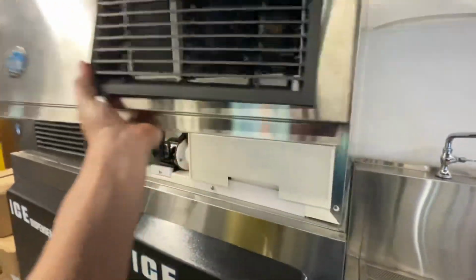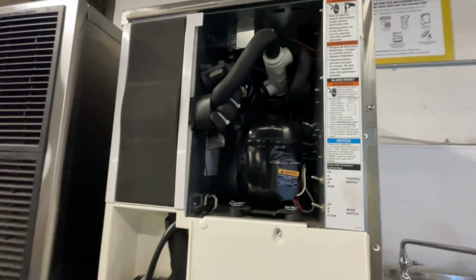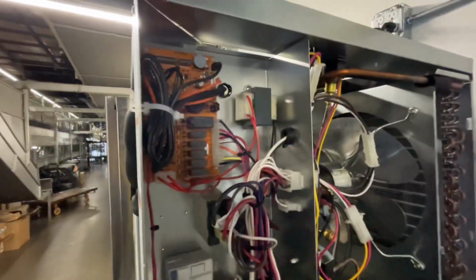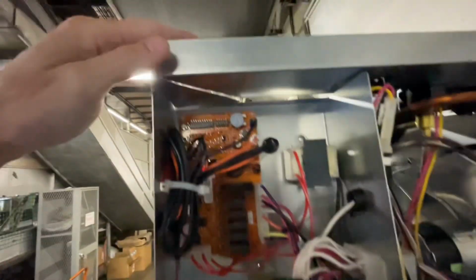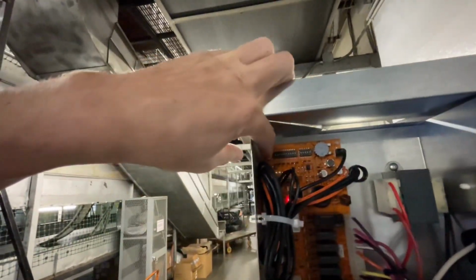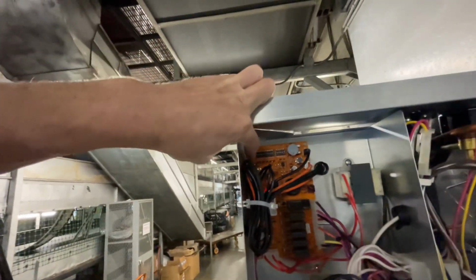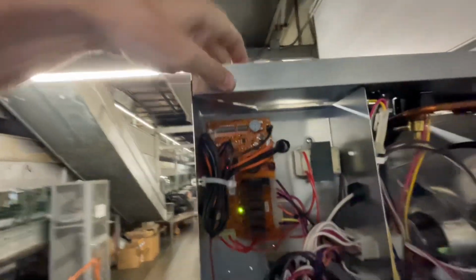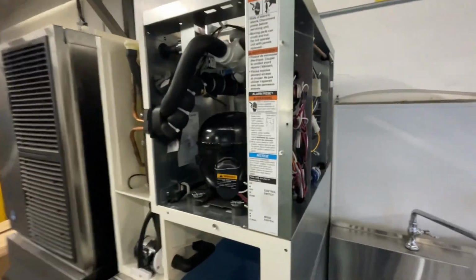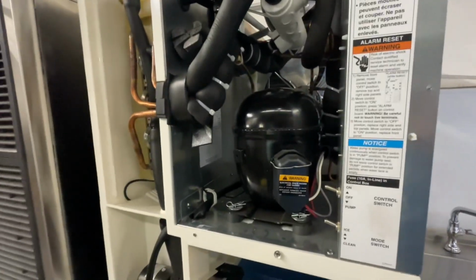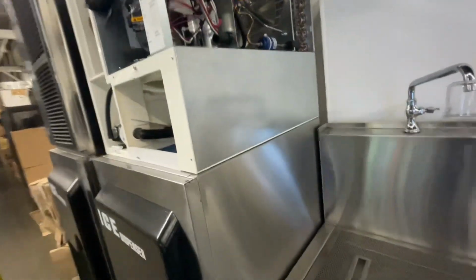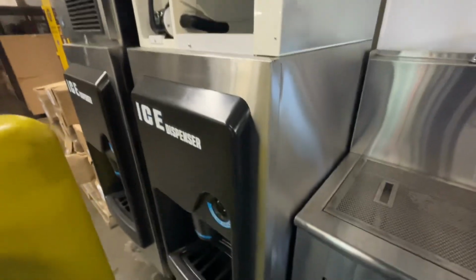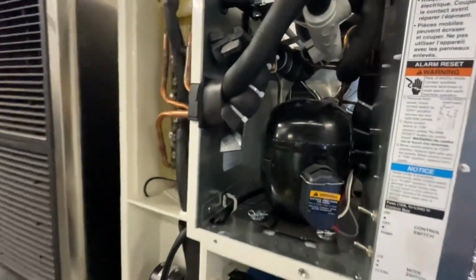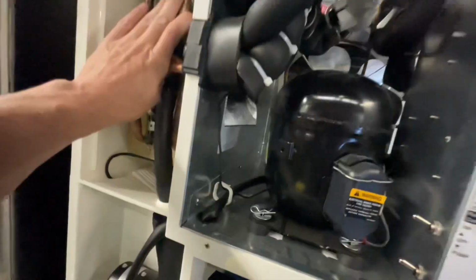Let's see why this thing is beeping 2 times. For those who don't know, this machine is off on 2 beeps, which means, if I can get this to reset, that harvest time exceeded 20 minutes for 3 cycles in a row. We gotta double check. All right, just double checked, it's actually 2 cycles in a row, so harvest time exceeded 20 minutes, 2 cycles in a row.